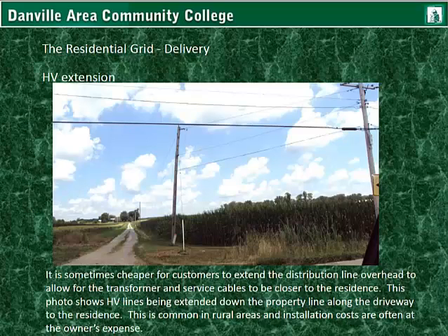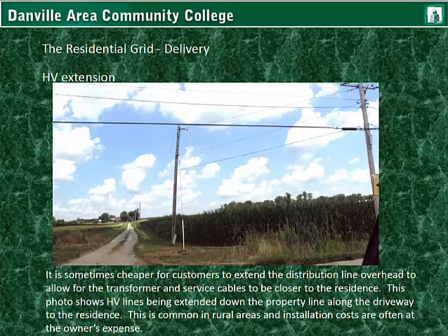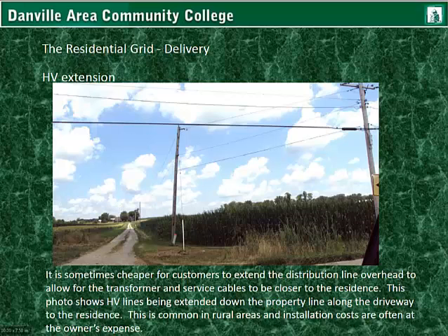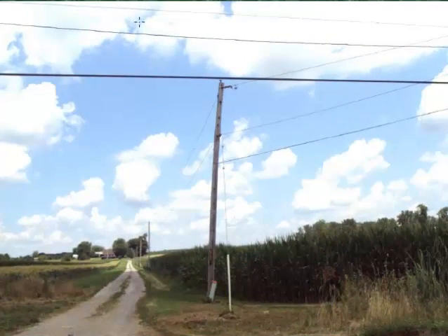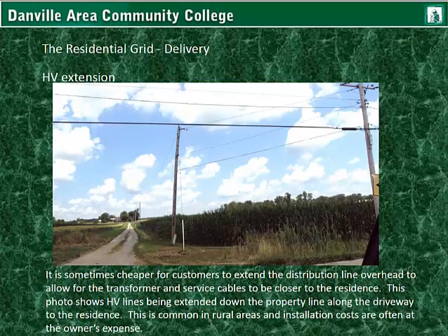High voltage extensions. It is sometimes cheaper for customers to extend the distribution line overhead to allow for the transformer and lower voltage service cables to be closer to the residence. This photo shows high voltage lines being extended down the property line along the driveway to the residence. This is common in rural areas, and installation costs are often at the owner's expense. This person lives on a farm far off of the road where the main lines are, so they put in overhead high voltage lines as an extension all the way down the drive to the home where the transformer would sit.